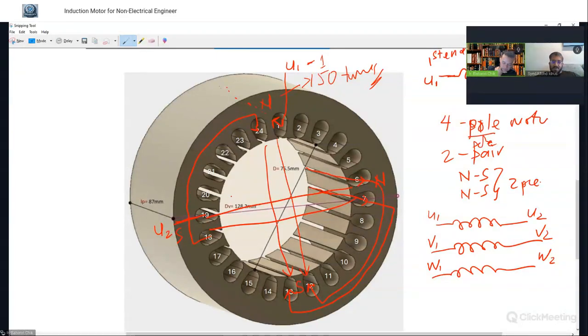So that means for 3 phase, 24 slots are needed? No, for a three phase, four pole motor, it needs 24. Okay, understand? Correct. So if a three phase two pole, which we'll see later, then you need fewer slots.